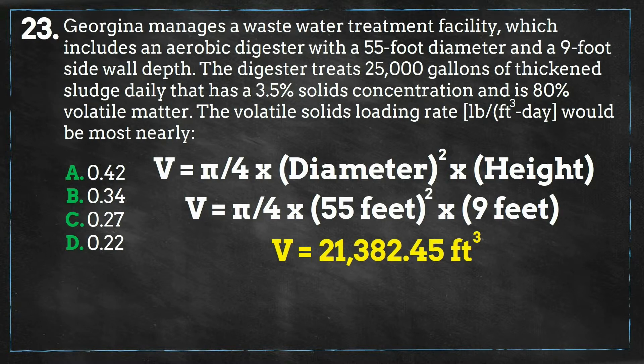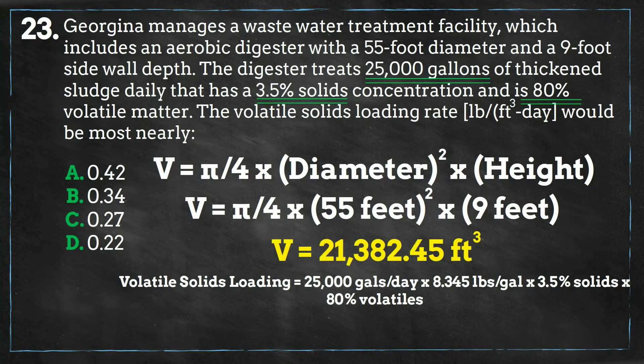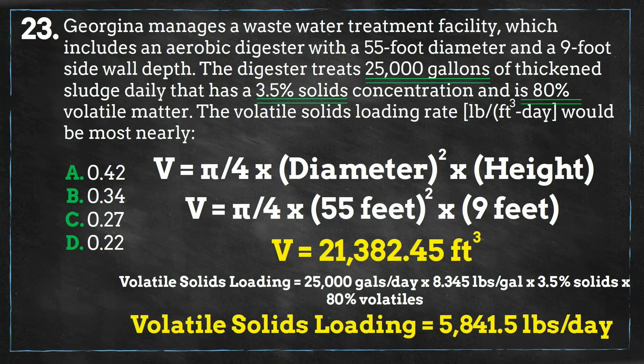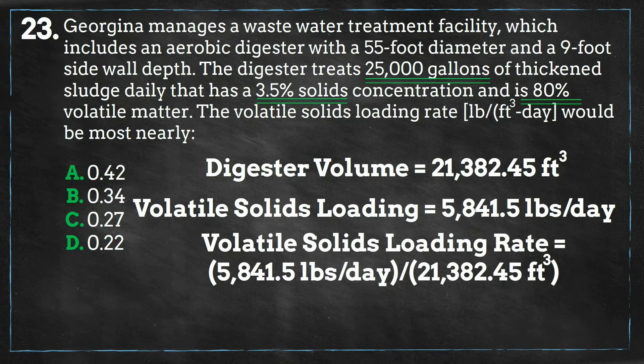Now let's solve for the volumetric flow rate of volatile solids. We are getting a flow of 25,000 gallons of sludge daily, and this sludge has a solids concentration of 3.5% and a volatile matter concentration of 80%. We can use the density conversion of 8.345 pounds per gallon of water and multiply all these values together to get 5,841 pounds of volatile solids per day. Dividing the total solids per day rate by the volume of the digester, we get 0.27 pounds per cubic foot per day of volatile solids, which is answer C.